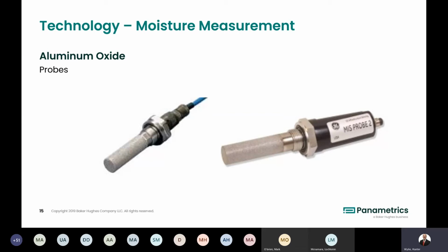Let's see, looking at a few additional things on here. Lachlan, would you like to speak a little bit on how to identify a failed ALOX probe? Okay. There's two real failure modes that you would see on an aluminium oxide. One is open circuit and the other is short circuit. So there is a diagnostic function on each of the sensors. For the probes on the left you see on the screen, we call it MH, and for the smart probe we call FH. And you can configure the displays of your analyzers to show this diagnostic function.